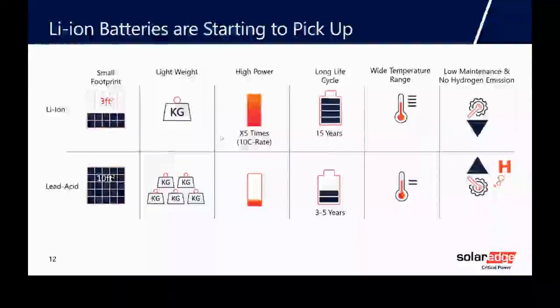They've got a long cycle life, and that is key. If you're working on demand response and you're cycling your systems up and down, discharging and recharging, VRLA is very poor—it can only do about 300 cycles, whereas lithium is over 3,000. So it's almost a must for cyclic applications.